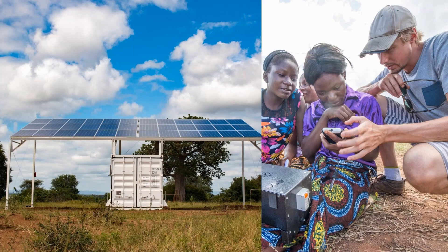What we've basically done at Standard Microgrid is to recreate that, but take the onus of people switching their appliances on and off away from customers. This is an example of what our power system looks like. We've tried to standardize everything as much as possible to reduce idiosyncratic costs. It's a 12 kilowatt solar array, containerized — we put down the container, build the power system with batteries and an inverter inside, and build a distribution grid out to the community. These are really rural communities in Zambia with no access to the national grid, replacing candles and kerosene. We connect about 150 households per system and provide AC power.